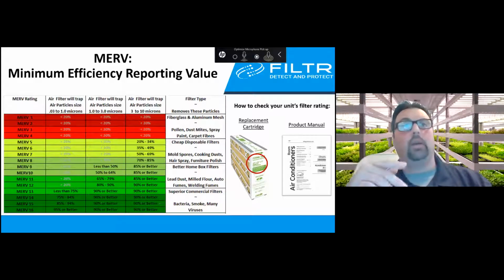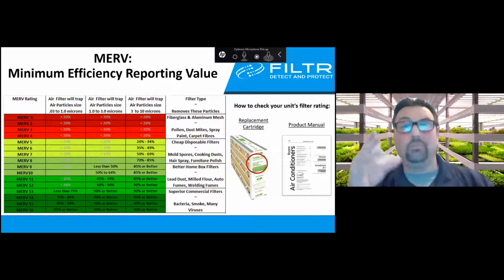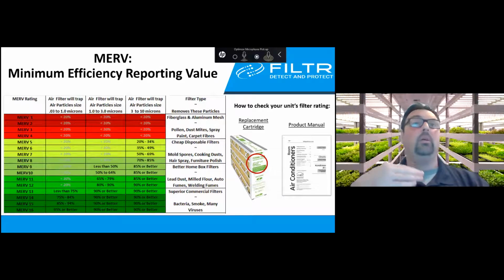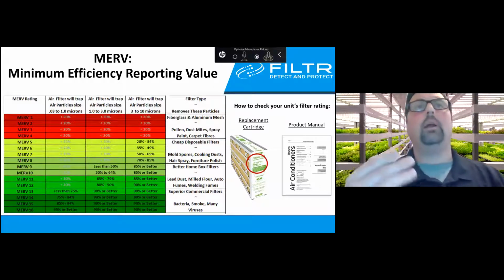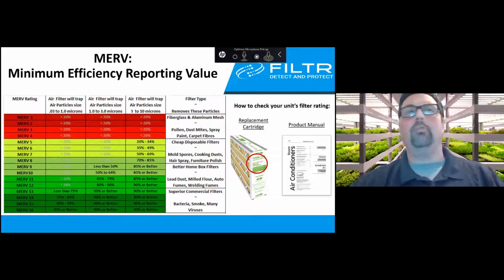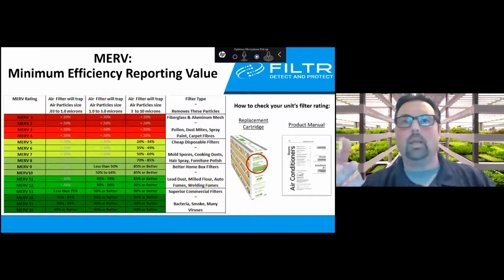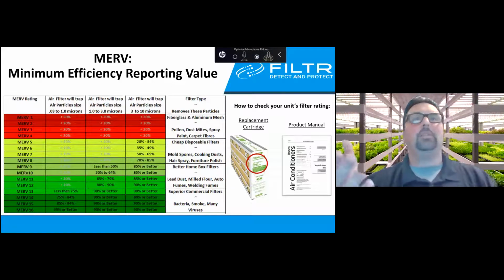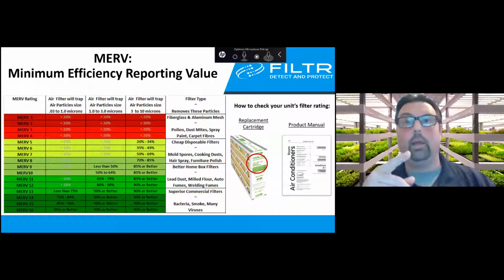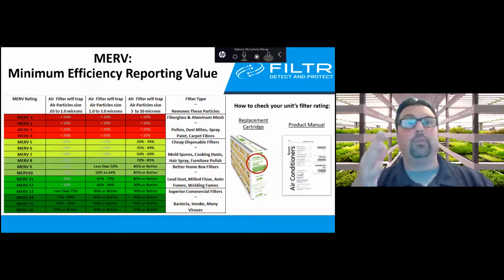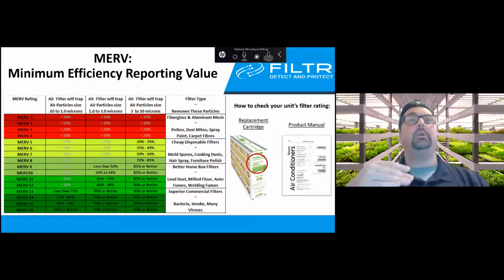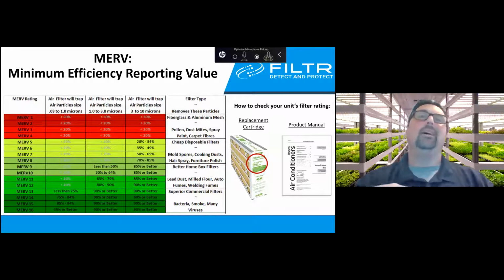You can see that the MERV rating scale goes from 1 up to 16. In reality, truth be told, it goes up to 13, and then you start getting into the HEPA scale. But if we're talking about 1 micron particles and larger, a MERV 8 rated filter, which is typically used in home and office applications, is catching less than 20% of what you need. So when you build your spot out and you have your air conditioners on your roof or your handlers in your hallway, that filtration rating is only going to capture so much. Higher rated filters, as you can see from the chart, capture more particles. Ideally you'd want to be at a MERV 13 because it's catching 90% or better of anything that's 1 micron and up.